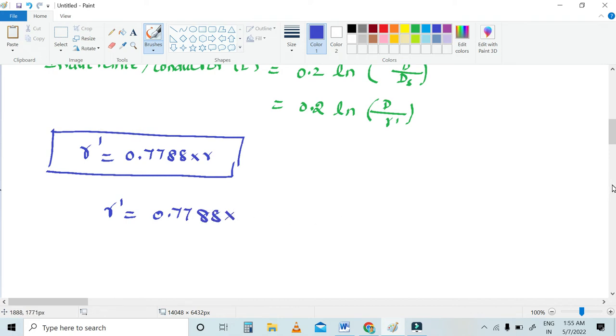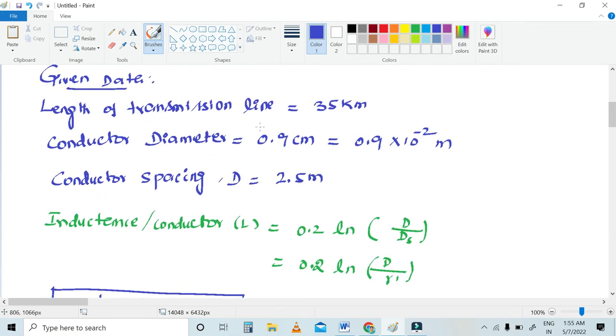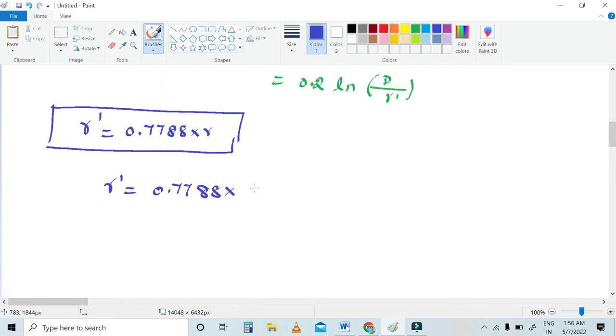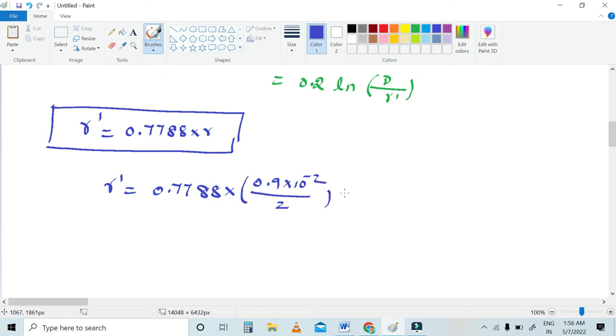The conductor diameter is 0.9 cm, so the radius r = D / 2 = 0.9 × 10⁻² / 2. Simplifying, r = 0.45 × 10⁻² meters, and therefore r' = 0.7788 × 0.45 × 10⁻² = 0.35 × 10⁻² meters. This is the r' value.